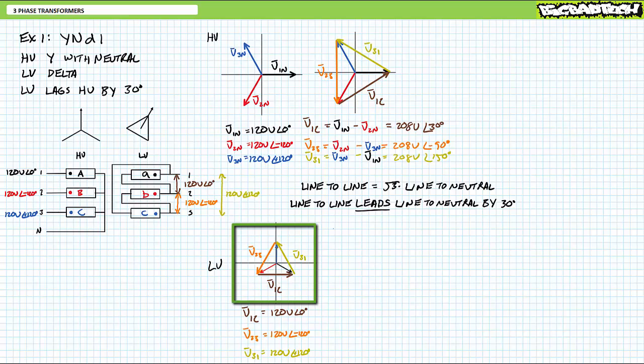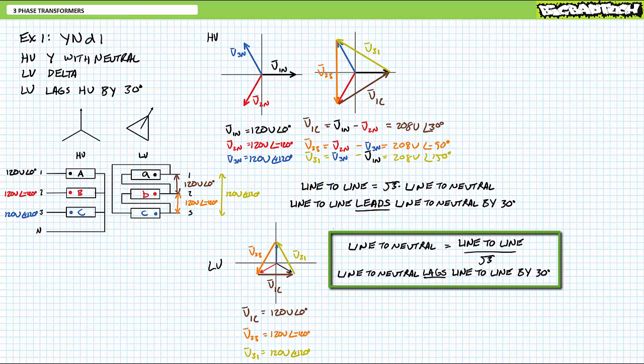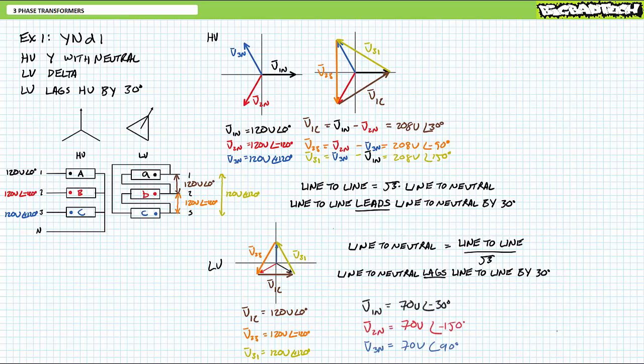To determine this new configuration's line-to-virtual-neutrals — the little virtual points inside the delta configured output — one could perform the reverse calculation. If the line-to-line voltages are roughly 1.73 times that of line-to-neutrals and lead the line-to-neutrals by 30 degrees, it stands to reason that the line-to-neutrals are one over square root three, or roughly 0.577 times the line-to-lines, and they lag the line-to-lines by 30 degrees. Doing so yields roughly 70 volts at an angle of negative 30 degrees, 70 volts at negative 150 degrees, and 70 volts at 90 degrees. The reference line-to-virtual-neutral for the delta configured output lags by 30 degrees — hence the one o'clock designation.